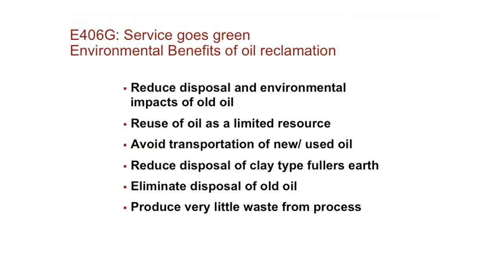Environmental benefits include the disposal. We reduce the disposal of the old oil and the refining of new oil as a limited resource. You avoid the transportation for the disposal, the refining, and the delivery of the new product, and you eliminate the complete disposal, however it would be disposed of, whether incinerated or sold as a byproduct. For this process, you produce very little waste, as compared to the old or traditional fuller's earth, where you purchase a clay fuller's earth, get 1 or 2 processes out of it, and then have to dispose of it in a landfill. This process you can reuse 300 to 500 times what you can the traditional fuller's earth material.